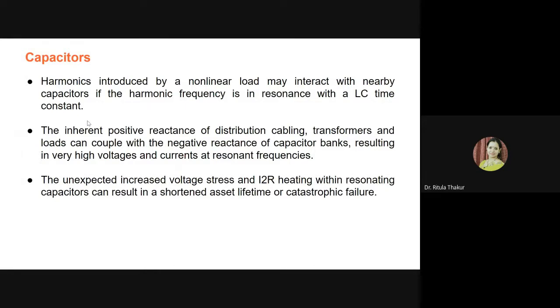cause I-square-R losses and eddy current losses, which cause heating, whether it is a power transformer, a cable, the metering equipment, the switchgear, or the capacitors. So ultimately, because of this heating and insulation failure, it will reduce the lifetime of all these distribution assets.